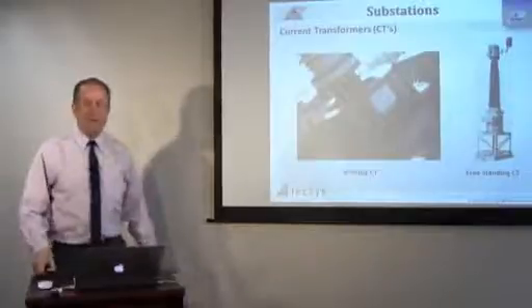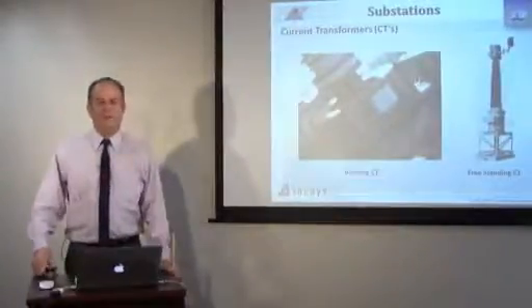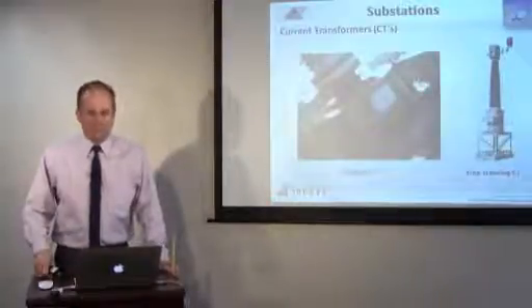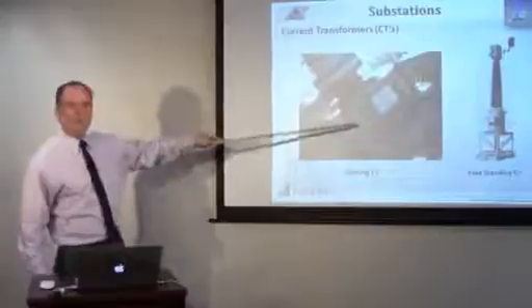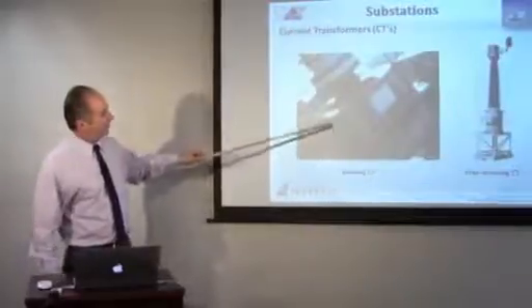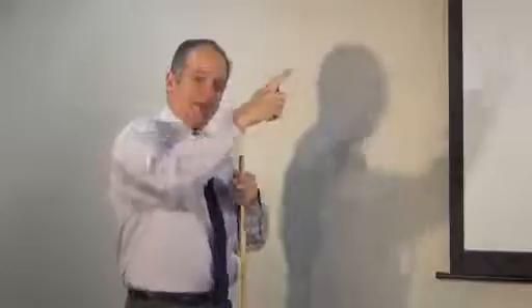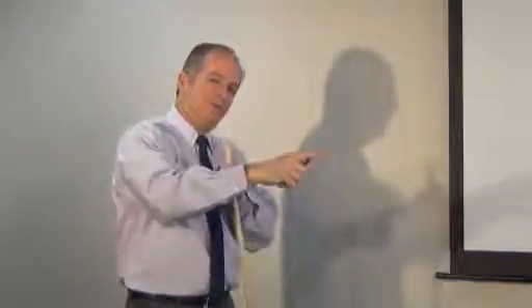Okay, the next area we're going to talk about are instrument transformers. I mentioned CTs and PTs. CTs are current transformers. PTs are potential transformers. In this case, we're going to talk about current transformers, CTs. And they're basically a coil, somewhat like a donut slipping over the bushing. The coil of wire picks up the magnetic field from the real current flowing through the main power line. And based on the strength of that magnetic field of the main current, tells us how much current is flowing in the main line.